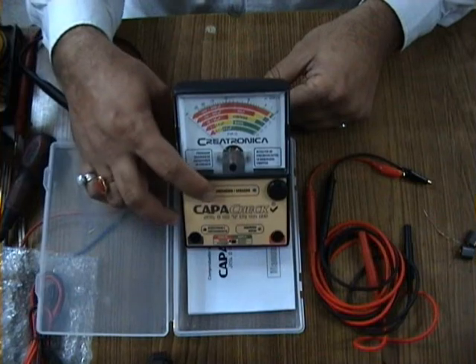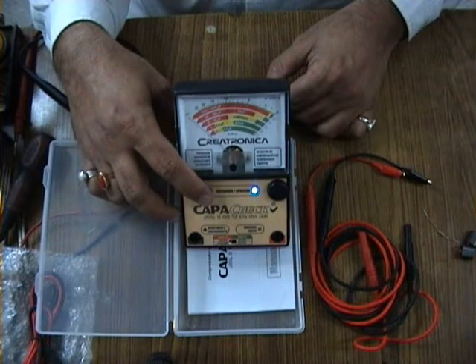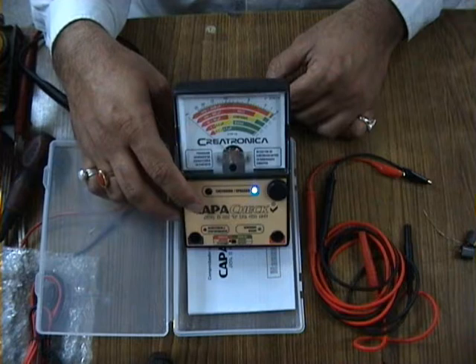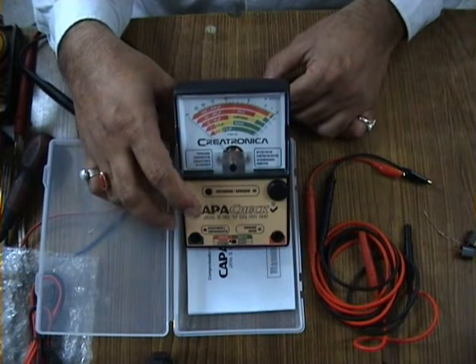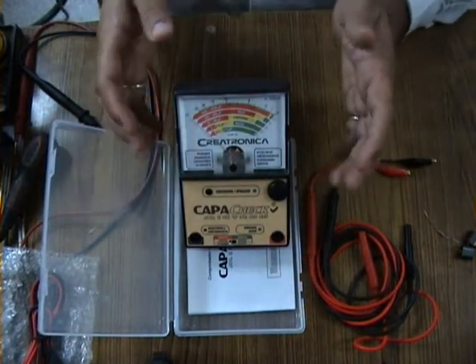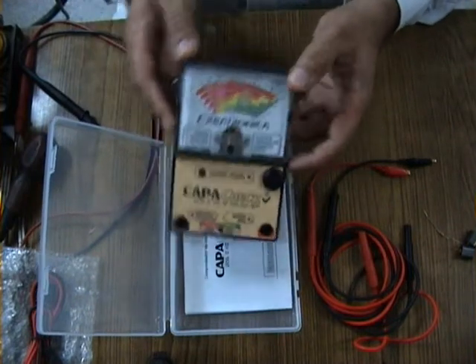One button press and the blue light comes up. To switch it off, you keep the button pressed for a second and it gives two beeps and switches off. Now my first inspection step is to always wobble the meter to see if there is any problem with the needle getting stuck to the glass surface. One of the meters I took out today has the needle actually stuck to the glass from shock. In this meter, the needle movement is pretty nice.